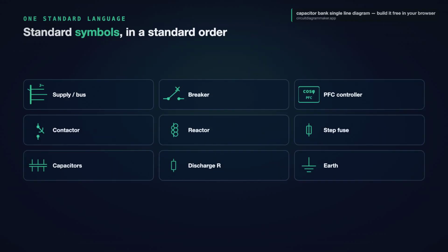And running underneath all of it, earthing and bonding. The bank enclosure, the frames, every metal part tied together and down to earth. On the single line diagram that shows up as an earth line reaching every step. Draw the earth every time. So step back and look at what you have. Standard symbols in a standard order. A supply source for the bus.